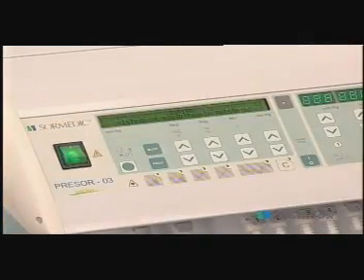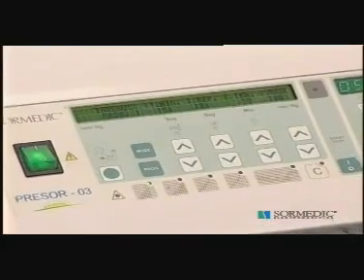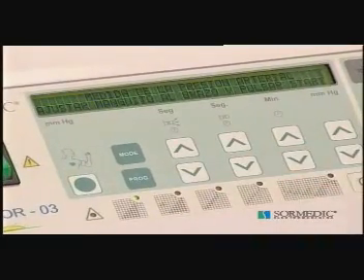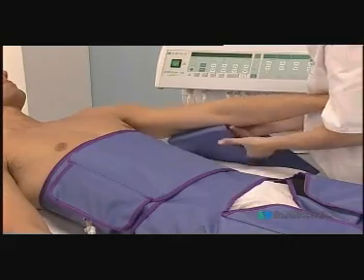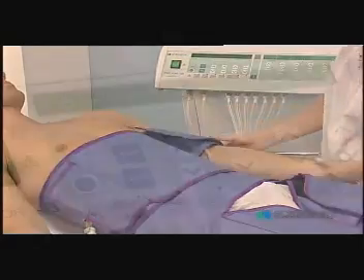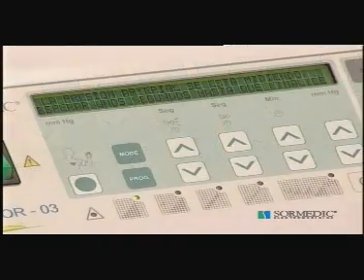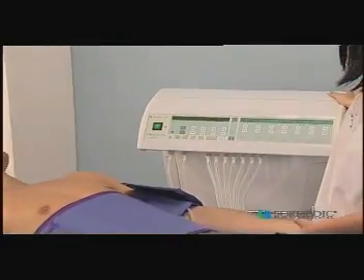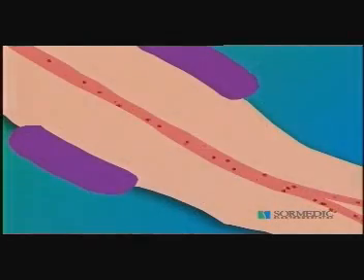One of the most important characteristics of Presor O3 Excellence is its capacity to adapt the applied pressure to the blood pressure of the person being treated. To measure the blood pressure, place the tubular accessory on the left arm above the flexing point of the elbow. Press the start key. The screen will show the message: blood pressure is being measured, please wait a few seconds. Presor O3 Excellence pumps air into the accessory until reaching a pressure sufficiently high to block blood circulation of the extremity.